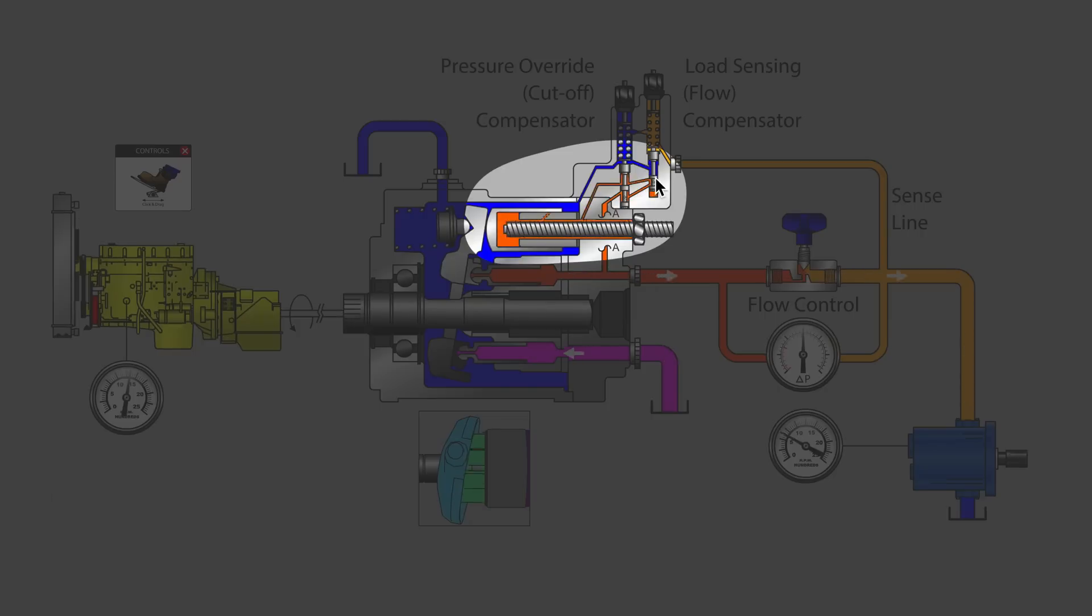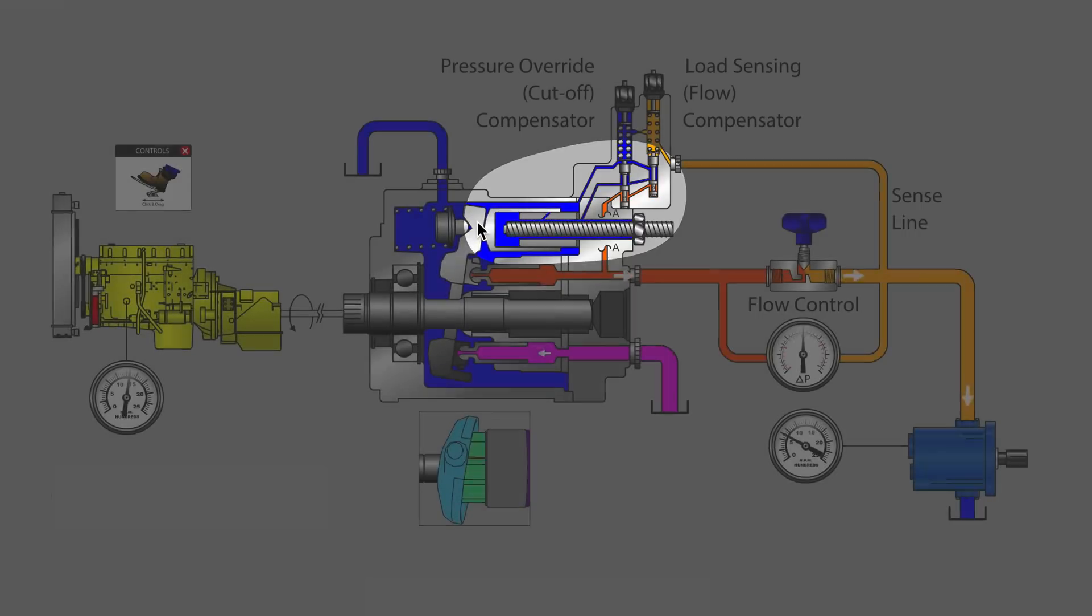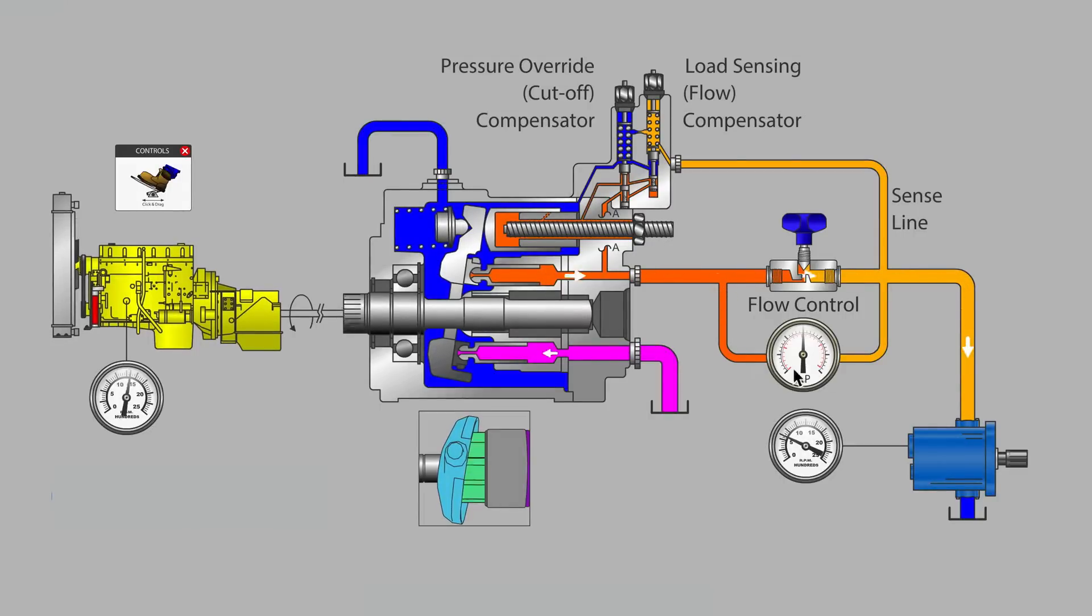The spool would pop up and direct control fluid into the control piston, destroking the pump slightly, reducing its displacement, and in so doing restoring—very quickly restoring—our desired delta P across the throttling valve, allowing our hydraulic motor to run at a very steady speed.